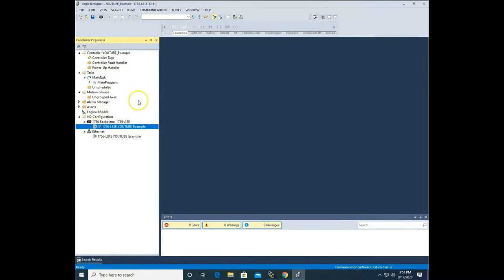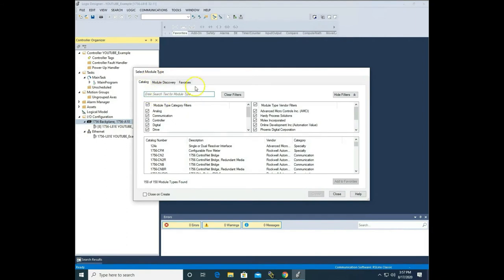I'm going to highlight '1756-IB16' — everything from the slash back — right-click and copy. I need to remember two things: it's in slot 0 and the module revision is 2.004. Going back to the main screen, we have to tell this PLC the cards inside it and where to find them. So I'm going to right-click the backplane, go to new module, and I can scroll through to find that card.